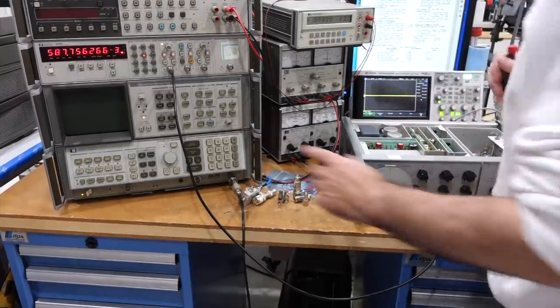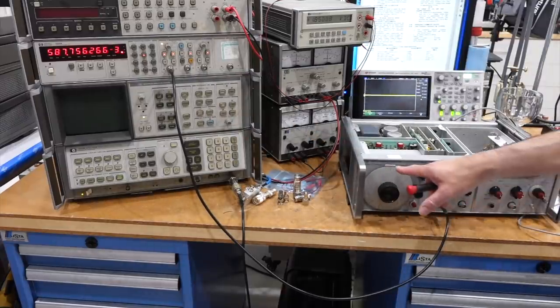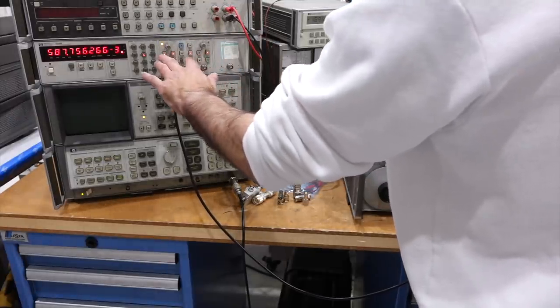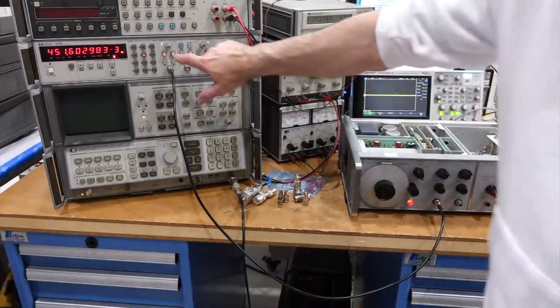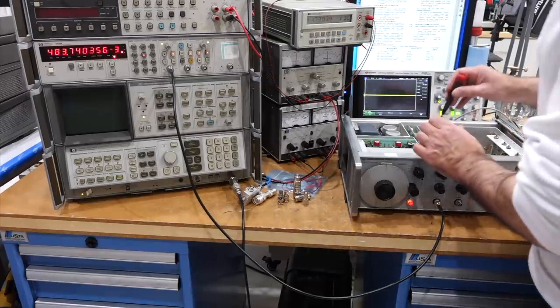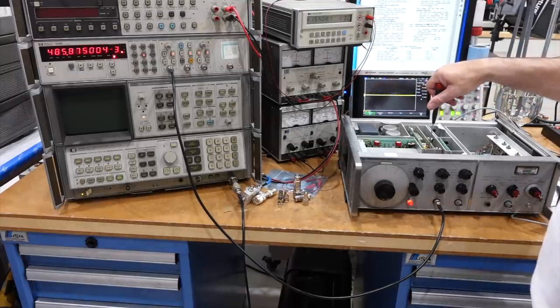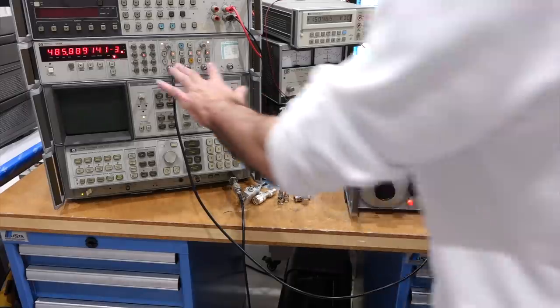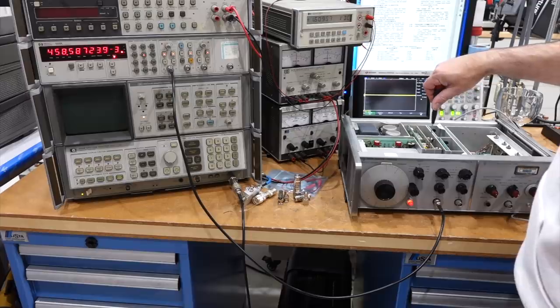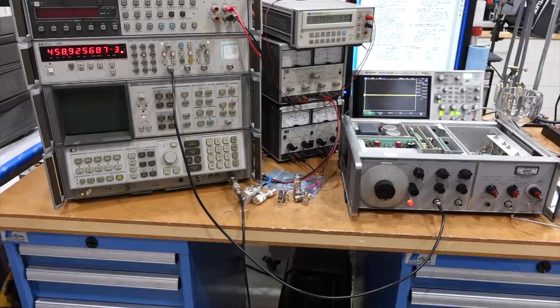The next adjustment is actually the symmetry. And we first get it at one second on square wave. And I should have half a second both ways. We measure the period before it going up and going down and going up, and vice versa, and it should be equal. So right now we have 450 one way and 480 the other way. So yeah, so that's definitely not right. It's 485 on one. I can really not move it. And it's 458 on the other.